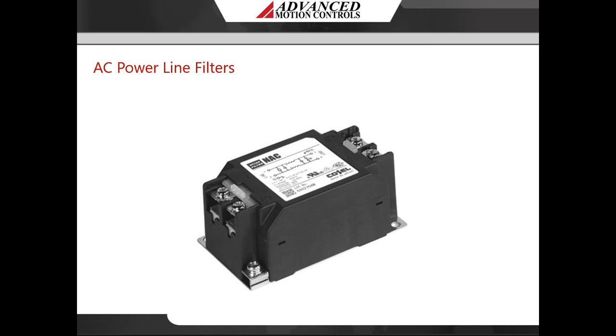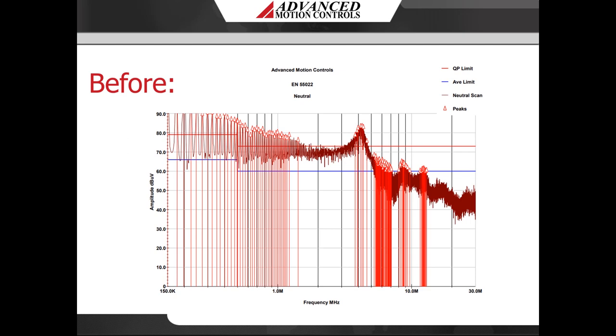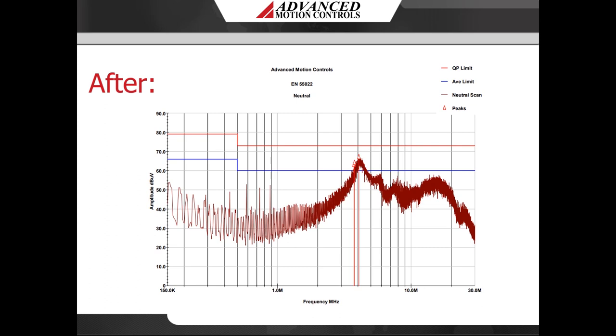It is possible for noise generated by the servo drive to leak onto the main AC power and get distributed to nearby equipment. AC EMI filters are effective at filtering high frequency noise from being conducted out over the AC power lines. By connecting a filter, noise on the AC line can be greatly attenuated. With the use of a single-stage AC power line filter, high frequency conducted emissions are greatly attenuated and meet the set emission limit. If further filtering is required, a two-stage line filter can be used. The purpose of these graphs is to display the effect filters have on emissions, serving as pre-compliance testing data showing how emissions are mitigated through the use of various filters.